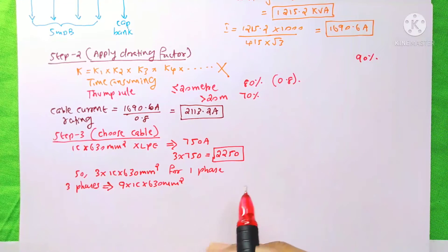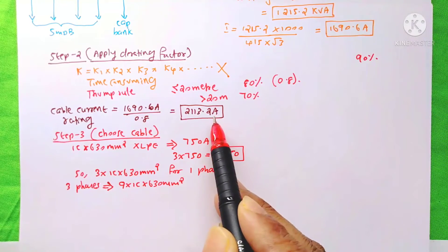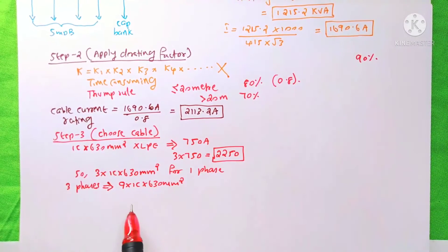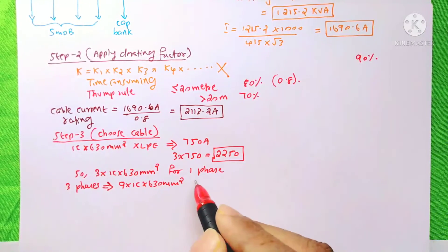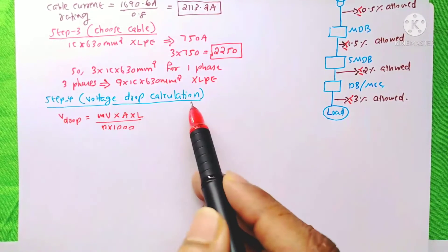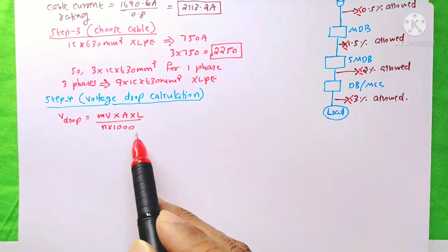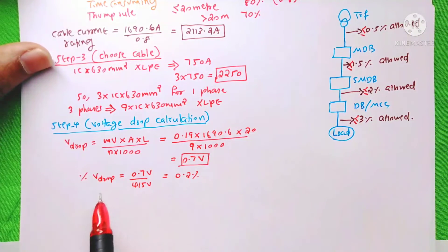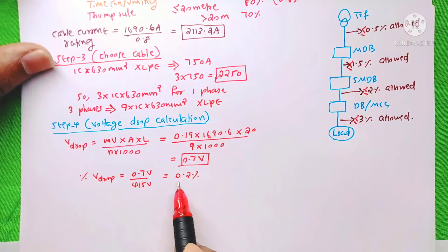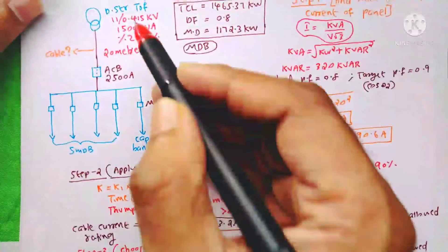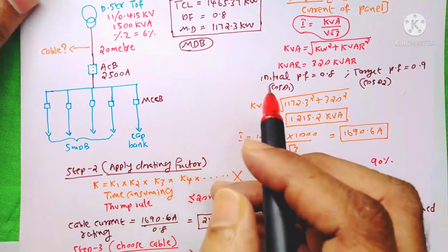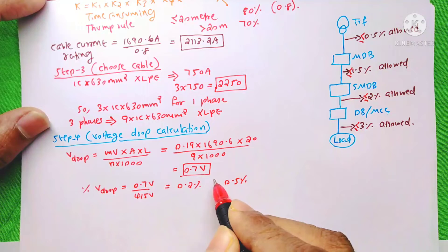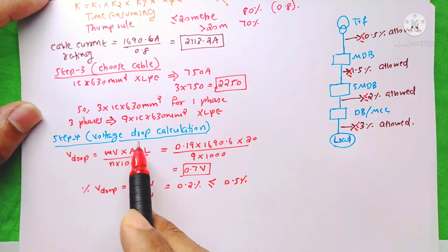Note that 2113.2 A passes through one phase, so for one phase we need 3 runs of 1-core 630 mm² cable. For three phases, 9 × 1-core 630 mm² XLPE cables are required. Voltage drop = (mV/A/m × length) / (n × 1000). Substituting all values gives 0.7 V, which is 0.2% of system voltage.